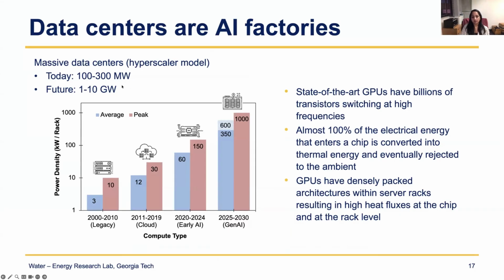The reason why this has become more and more of a thermal issue is because if we look at the power densities for the planned racks from companies like NVIDIA, for example, you start to see that the kilowatts per rack is going up significantly. This is on a log scale. It's gone from about 10 kilowatts per rack to 100 kilowatts per rack currently, and now projecting to 1 megawatt of power within a rack. So future data centers will be as large as about 10 gigawatts within the entire data center, with multiple 1 megawatt racks within it.